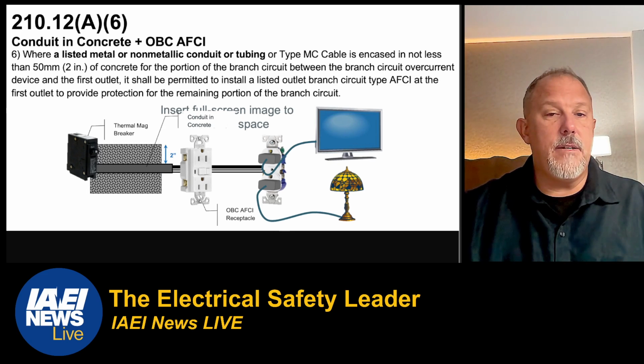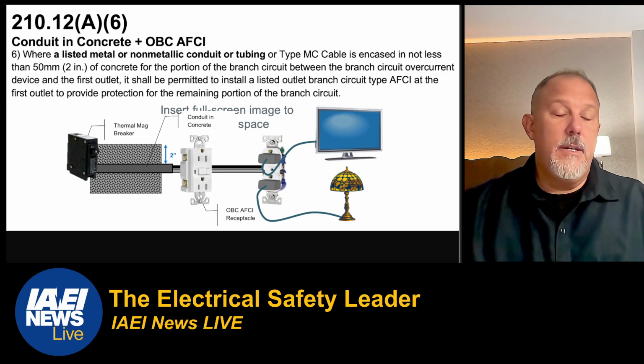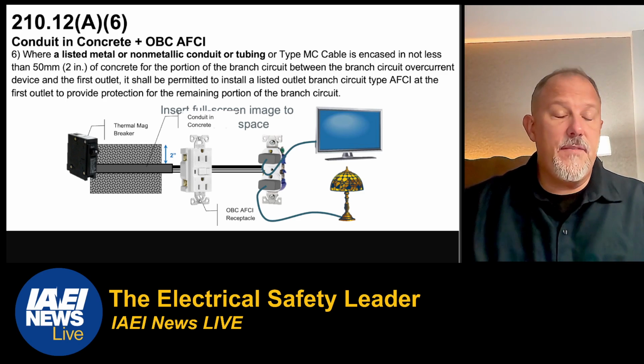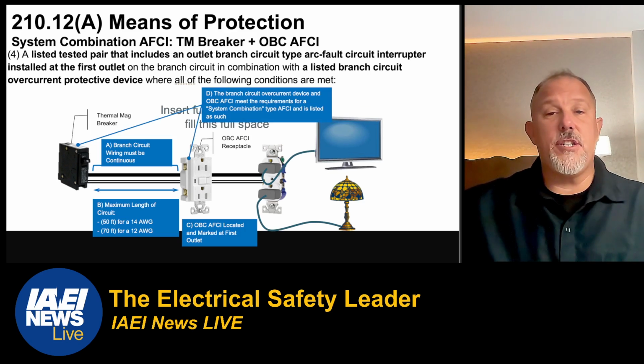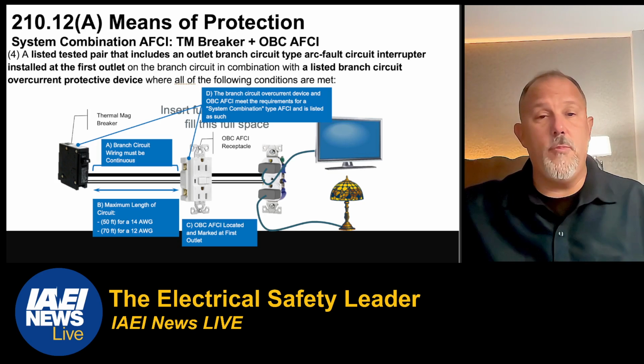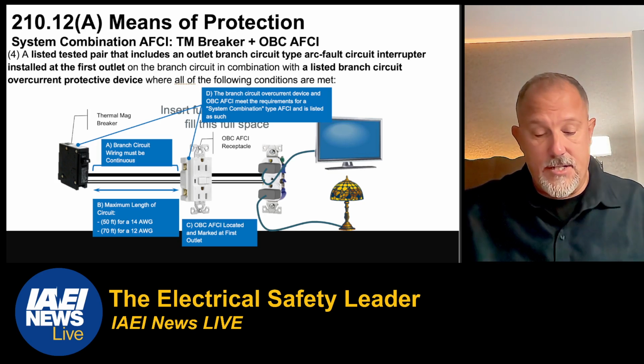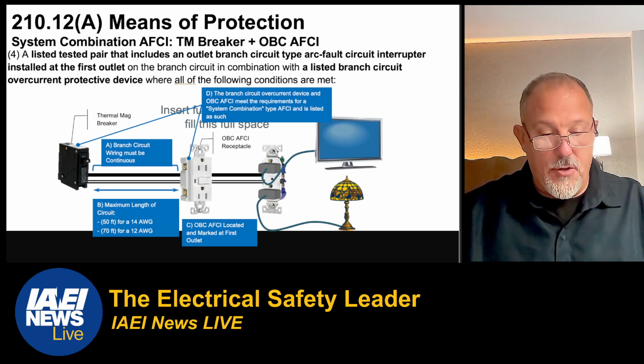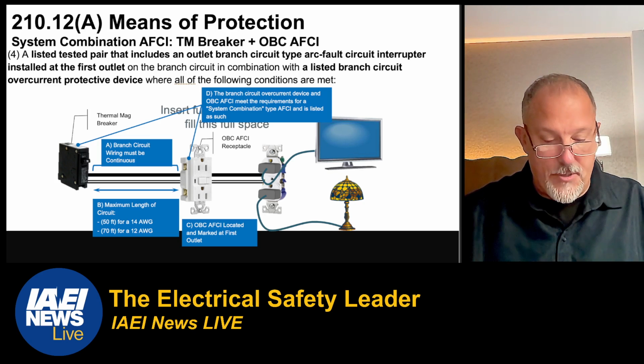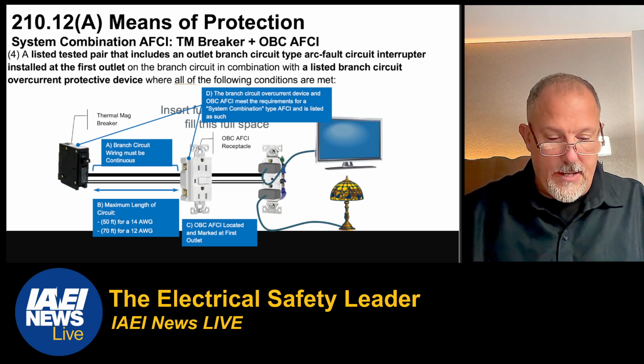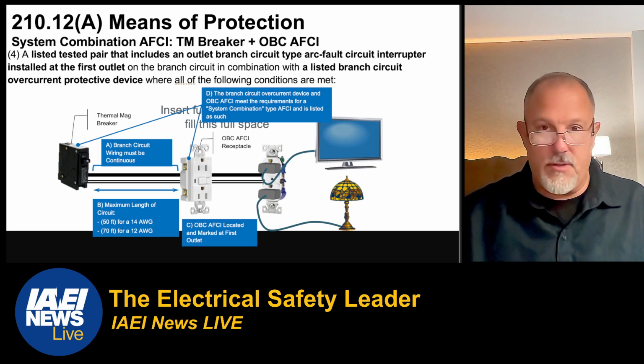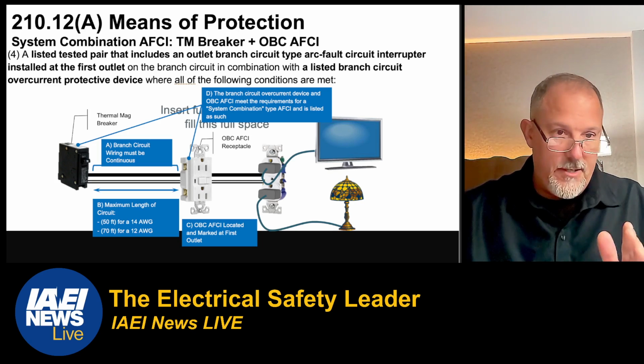And then 6 is the concrete. So just keep in mind that if you have that system combination, AFCI paired up with an OBC, there are limits associated with that which you're allowed to have for your AFCI protection. You can't go beyond, and those limits are still the same as they were last cycle. So none of this changed in reality.